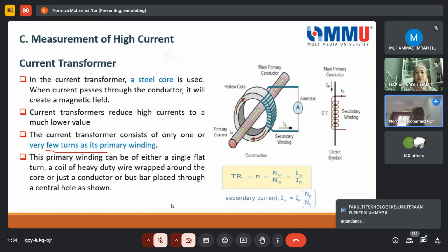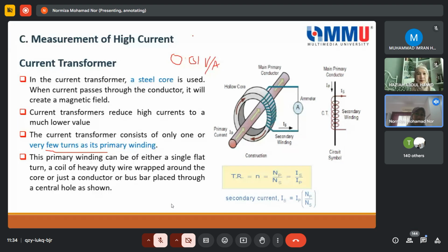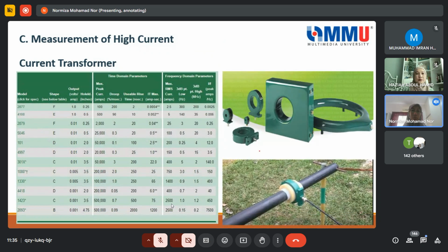But the sensitivity, we call it, is normally 0.01 volt per amp. And then this is for higher current, but for lower current, we can use 0.1 volt per amp. So it depends on the current measurement that you want to have. If the current is more than 1 kilo amp, then normally we use this one. If the current is less, then we use this one.